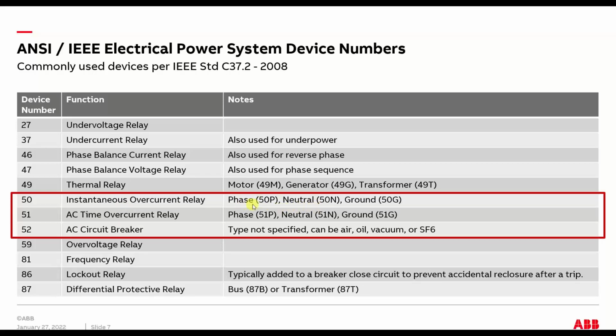It can be broken down even further into whether it's instantaneous for a phase, instantaneous for a neutral, 51's time. So this would be a time overcurrent for a neutral, time overcurrent for a ground. And then the rest of these are non-overcurrent protection type functions: overvoltage, 81's frequency. 86 is a pretty important one. It's a lockout. 87 is differential protection. So in my opinion, about 90% of the time, the devices you're going to see are in this list.